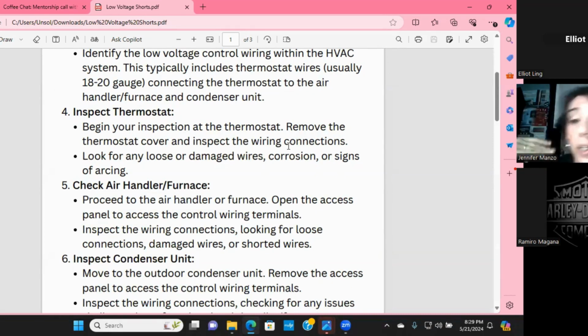And then you're also looking for damaged wires. Is there any charring or corrosion or mouse chews? Is there any spot on the wire where the insulation is broken, causing an arc? So we have a thermostat, which is essentially a contactor in a way where it takes a complete circuit to run the thermostat. If you have an arc between the completion of the circuit, you're going to have problems that are intermittent. So it's only going to happen when you put the thermostat cover on, or it's only going to happen when the thermostat kicks in. There's going to be many times where you'll see intermittent failures in thermostats, and if it's not just a bad thermostat altogether, those are typically caused by damaged wires.